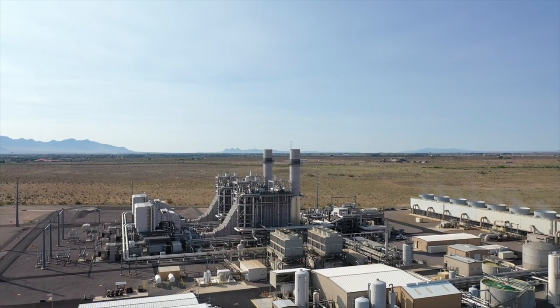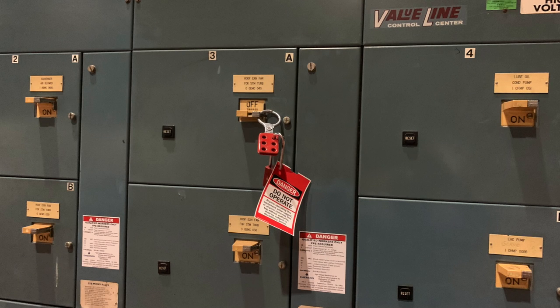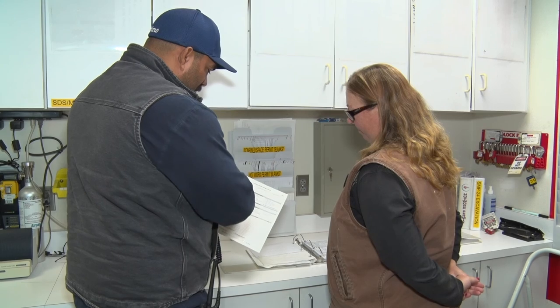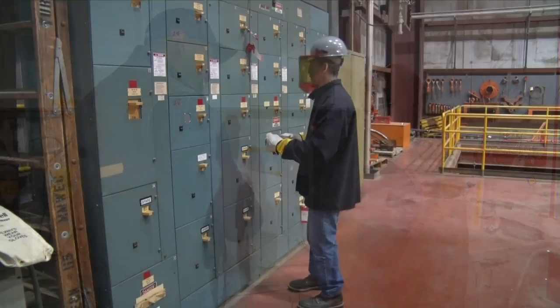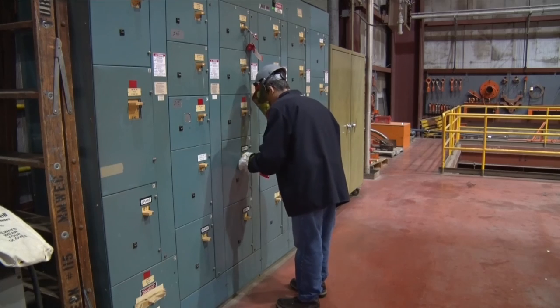Hazardous energy control is an important safety precaution at this facility. A lockout-tagout procedure is designed to protect personnel from exposure to hazardous energies, including electrical, thermal, hydraulic, and pneumatic, as well as the accidental startup of equipment or machinery being worked on. If you're working on equipment that requires lockout-tagout, the control room will review the lockout with your supervisor. The control room will arrange to have all lockout-tagout performed prior to the start of the work.